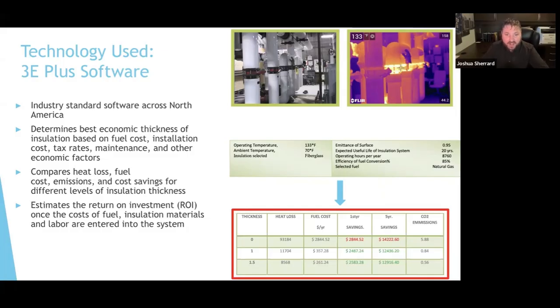This facility is losing 93,184 kBTUs per year. We believe they're spending fuel costs of $2,844.52 and emitting 5.88 metric tons of carbon by not having these items insulated—and this is a low-scale natural gas system. Just by installing a 1-inch insulation system, we can reduce the heat loss to 11,704 kBTUs, saving roughly 82,000 kBTUs per year.